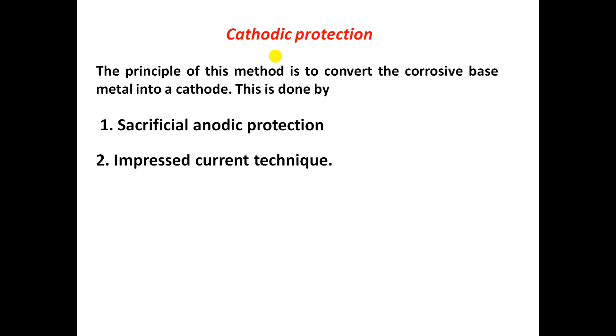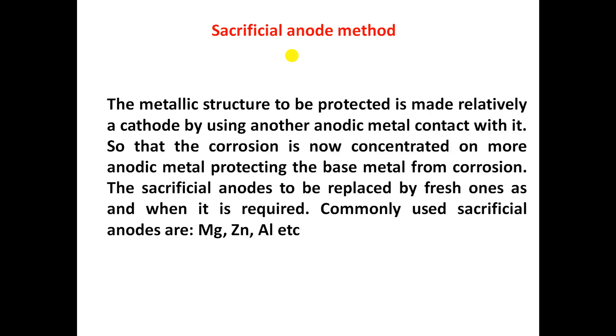Cathodic protection is done by two methods: the sacrificial anodic method and the impressed current method. In the sacrificial anodic method, the metal structure to be protected is made relatively cathodic by using a more anodic metal in contact with it, so that the corrosion is now concentrated on the more anodic metal, protecting the base metal from corrosion.